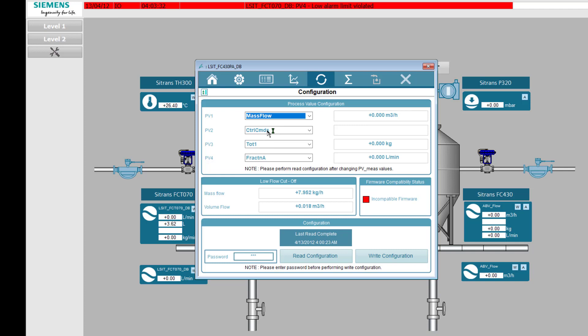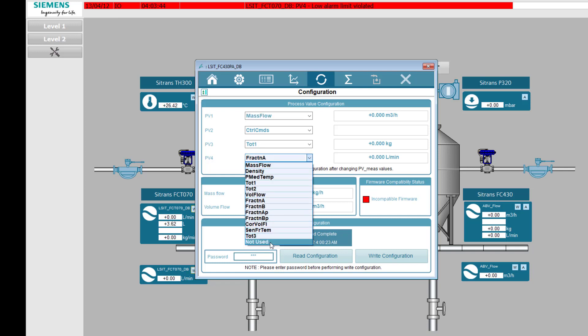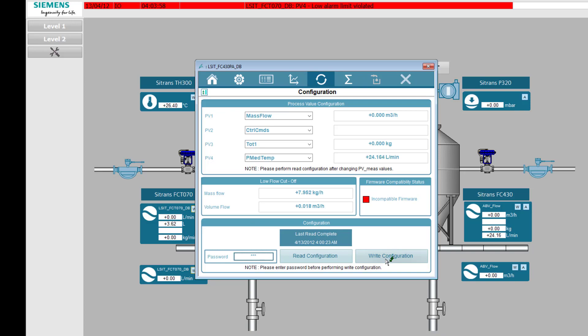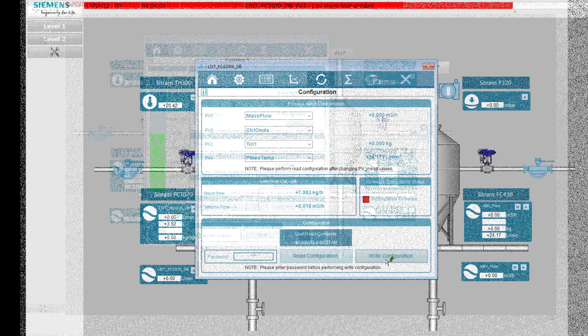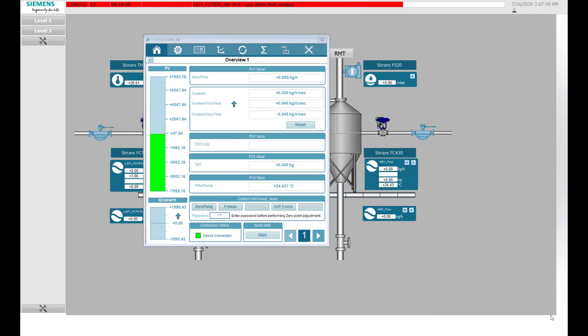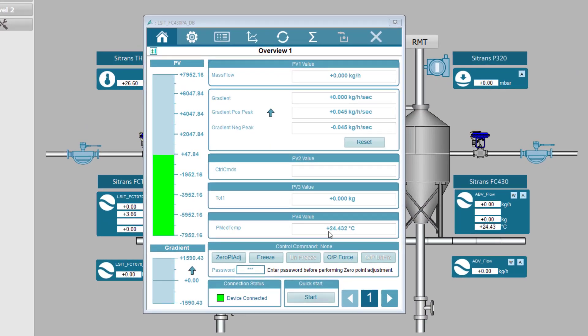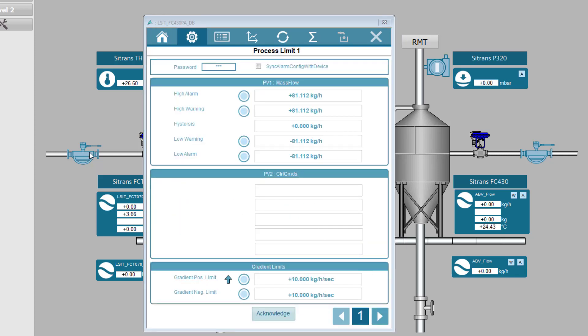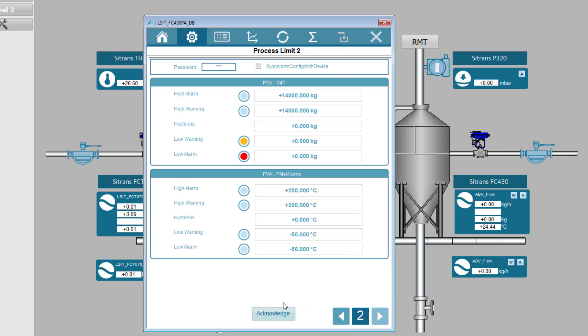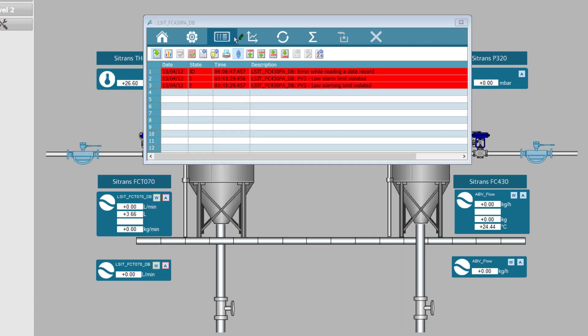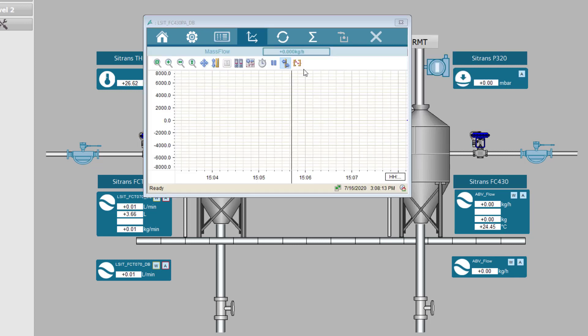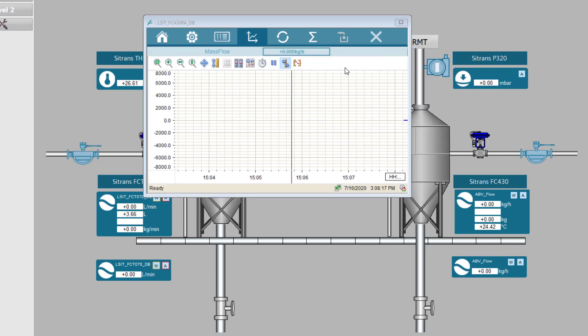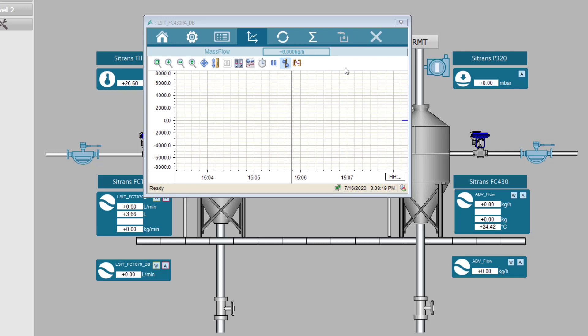You may not need it all of the time, you may want to keep that hidden, but I've got it here. And you can put one of the temperatures in there. When you have done that you need to write that to the device. The first thing you need to do is put in the password which is 2457 and then write that to the instrument. So it is writing it to the block but also to the instrument. Once you have done your download you can see here it has changed your units and also if I go to my alarms now I've got an alarm for each one of those process values and I can change those and acknowledge them from this screen. I have my alarm banner, my trends and if I had totalisers and batching selected I would have the control functionality for those as well.